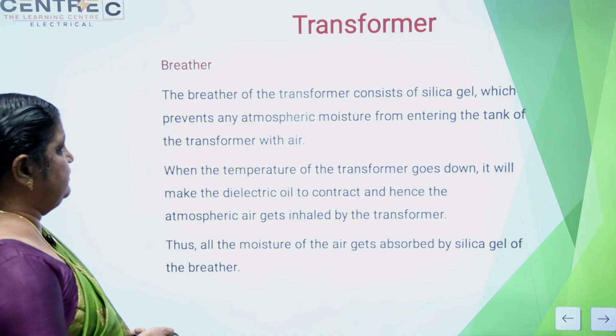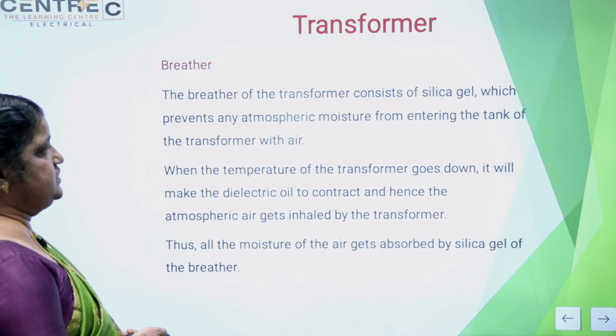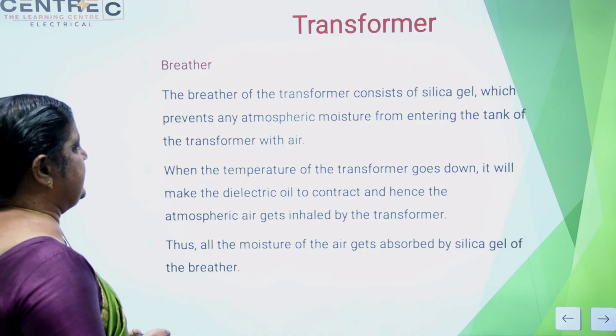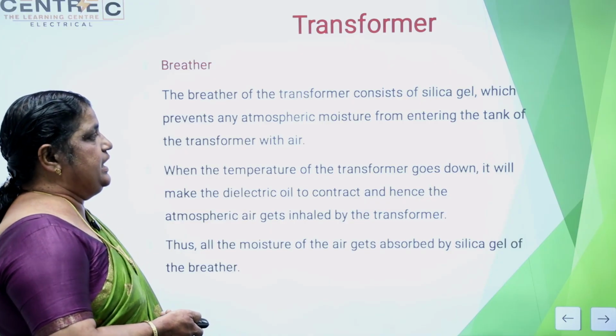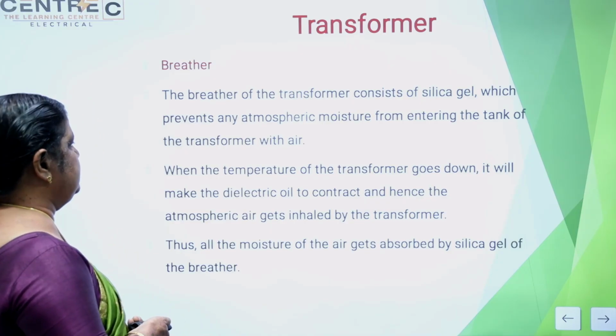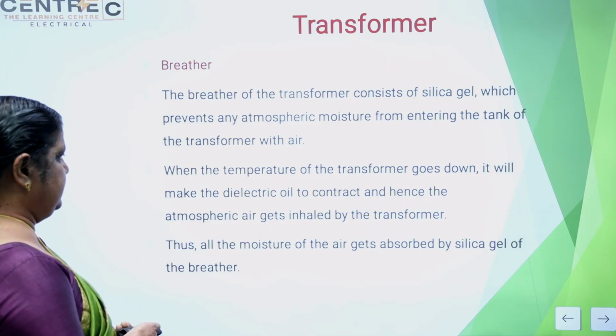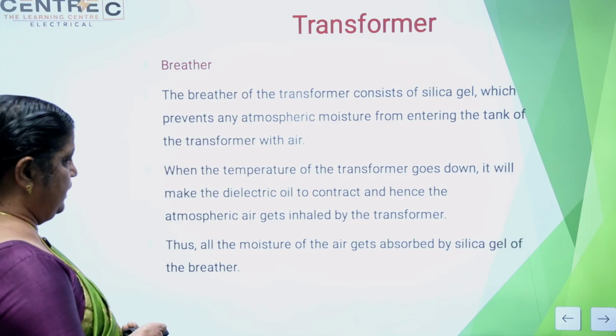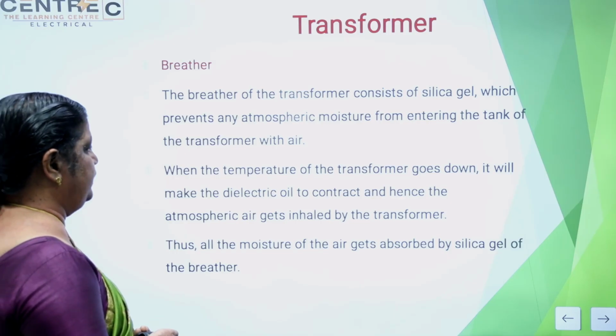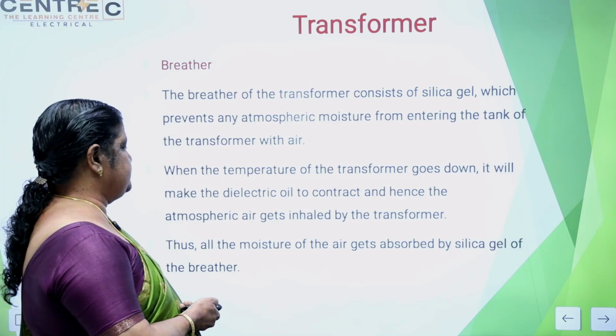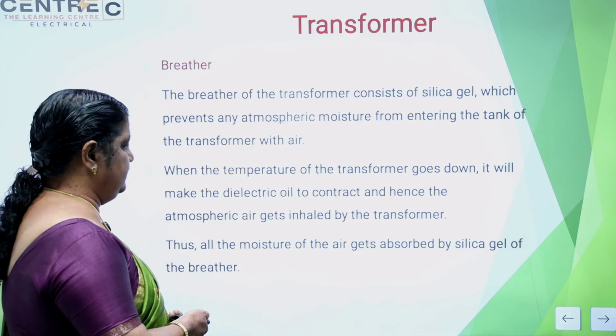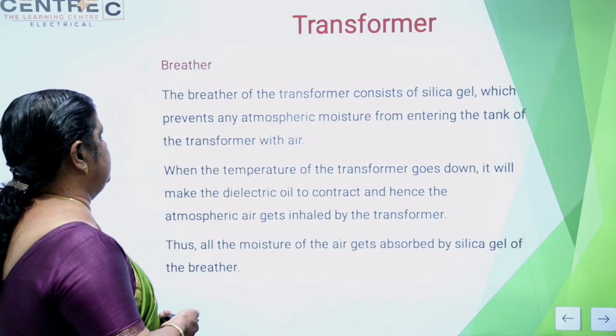Then the breather of a transformer consists of silica gel, which prevents any atmospheric moisture from entering the tank of the transformer with the air. When the temperature of the transformer goes down, it makes the dielectric oil contract, and hence atmospheric air gets inhaled by the transformer.